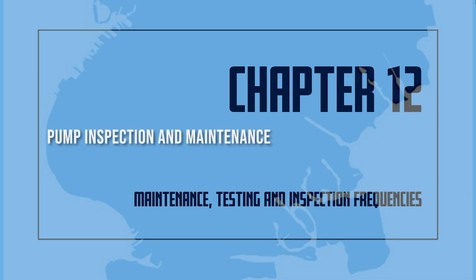Pump inspection and maintenance. In order to ensure the reliable operation of the pump in the case of an emergency, regular inspections and maintenance shall be conducted by the certificate of fitness holder. The pump should be activated each week and run for 10 minutes in accordance with the manufacturer specifications to ensure that it is functioning properly.